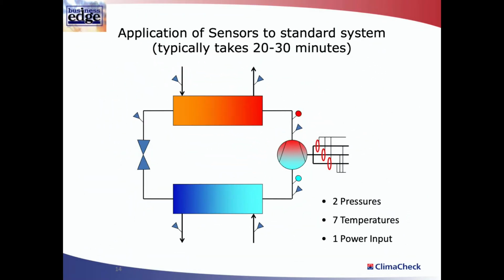You simply connect temperature sensors using a heat paste and an insulating material, all of which is supplied. Take voltage and amperage at the compressor or bank of compressors input, and also pressures, high pressure and low pressure, with easily fittable stainless steel transducers for conventional refrigerants and also for ammonia. These are suitable for high pressure refrigerants as well, such as R410A.